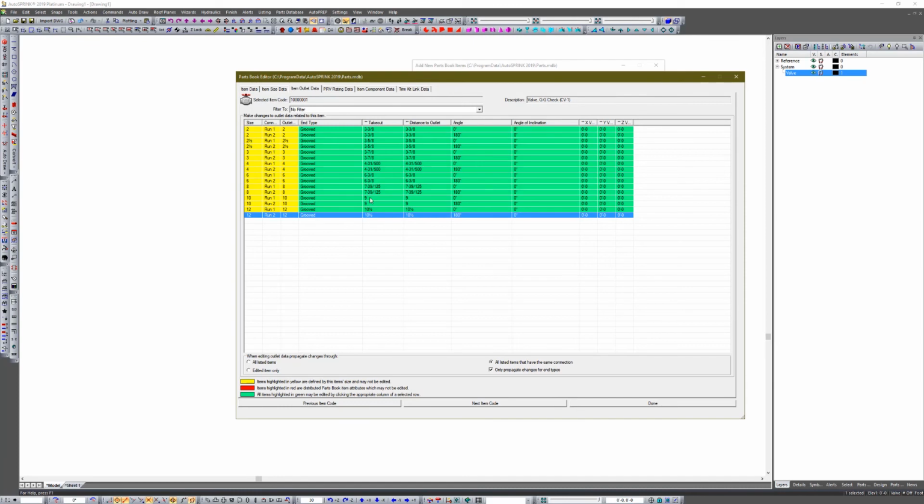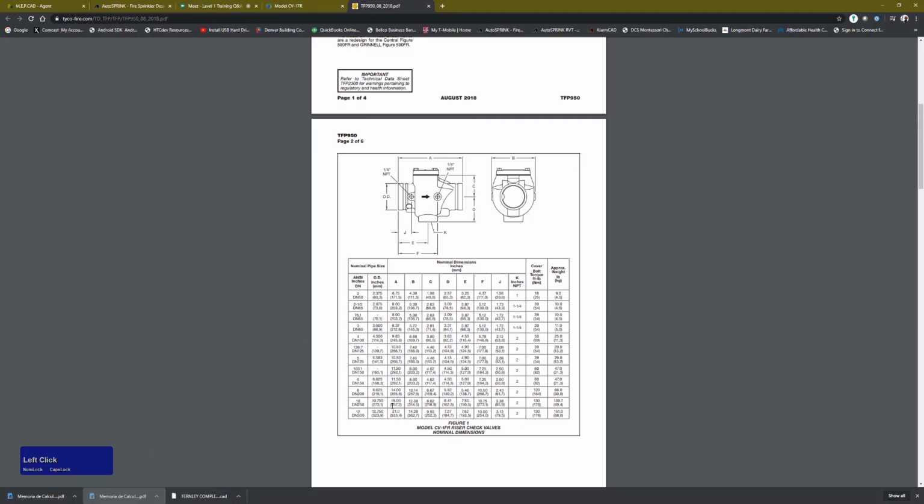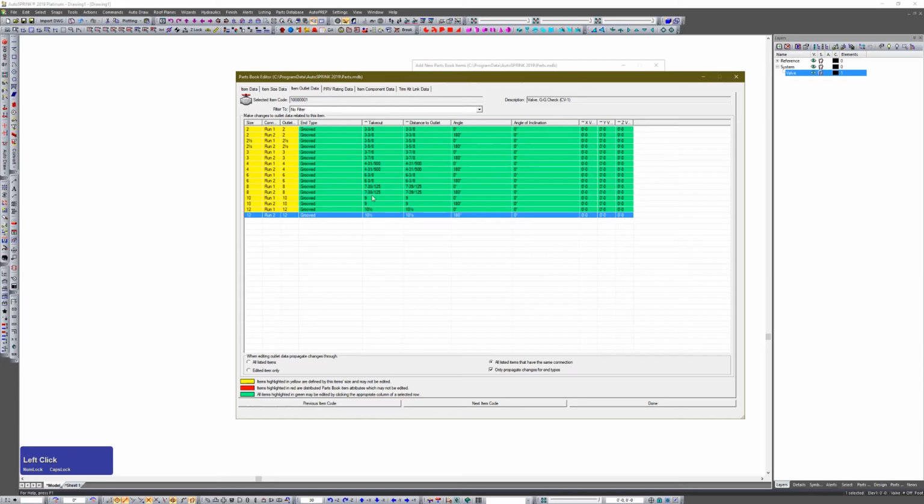It looks like most of these dimensions are appropriate for this valve that we just cloned. I'm going to just double check that the 10-inch should have an 18-inch takeout. End-to-end takeout, 18, yep, 14, so then the 8-inch I should have 7 and 7. This is a little off. Okay, so the 8-inch, I want to adjust this to be exactly 7 inches and 7 inches. Whoops, 7, 7, 7. Okay, now I'm not going to bother with the 6 and 4 and 3.